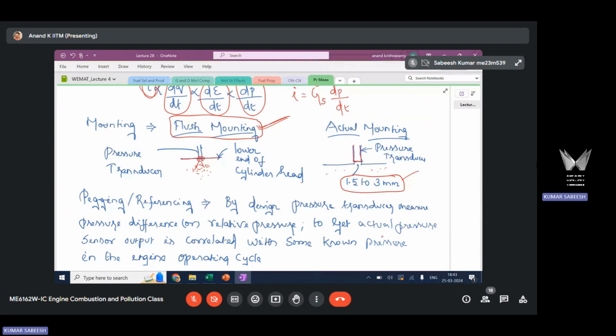So here, when you mount the sensor, you are actually creating a passage. There are problems here. Although you minimize the transient heat flow effect, through this channel or a small passage, you may have pressure oscillations. These pressure oscillations may result in some inaccuracies in the pressure value measured.